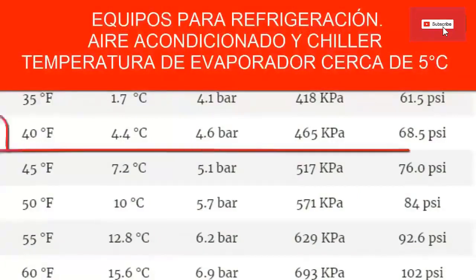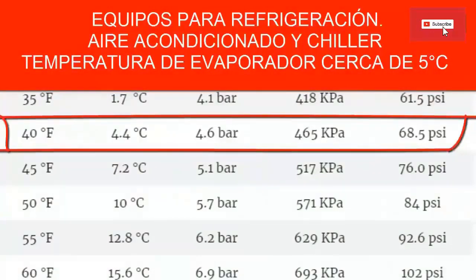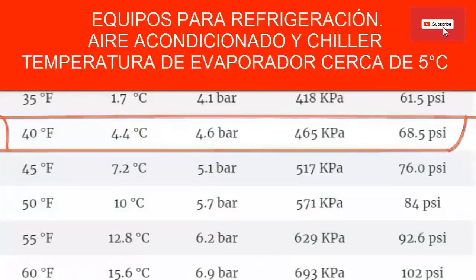That value is equivalent to 2.5 bars. For a high temperature system — refrigeration without freezing or air conditioning — we are going to have an evaporator temperature of 4.4 degrees Celsius, approximately 40 degrees Fahrenheit. Looking in the table, the low manometer should mark approximately 68.5 psi, which is equivalent to 4.6 bars.